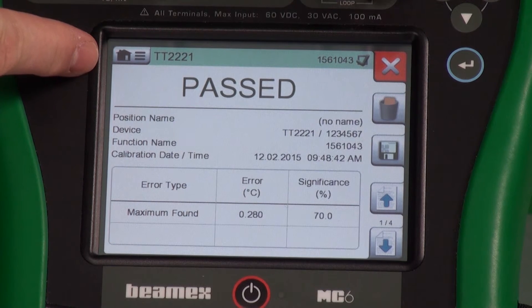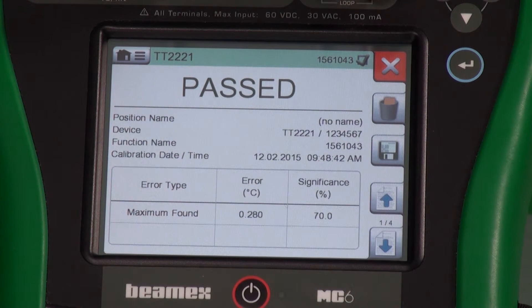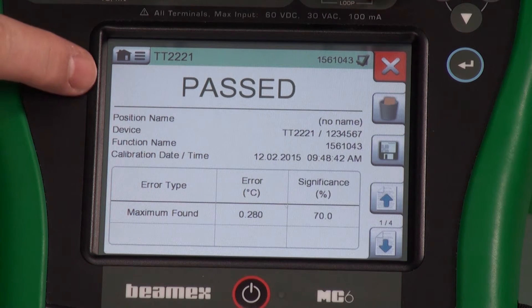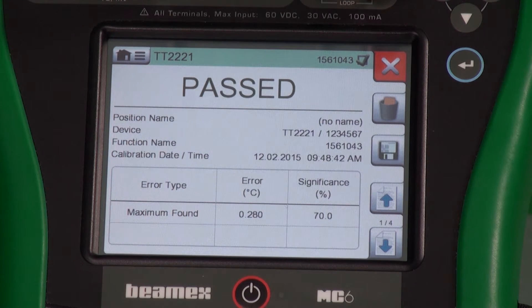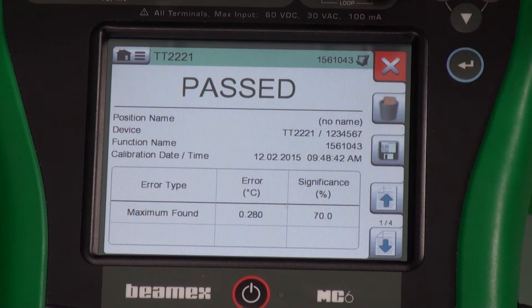Did it pass or fail? We can look right here — passed is obvious, it's a big 'Passed' in green. If it failed, it would say 'Failed' in red with the same font size. We get a rundown of the calibration event, our maximum error, and our significance. The significance is how much of our error tolerance we actually utilized. So we used 70% of our tolerance that was available to us.